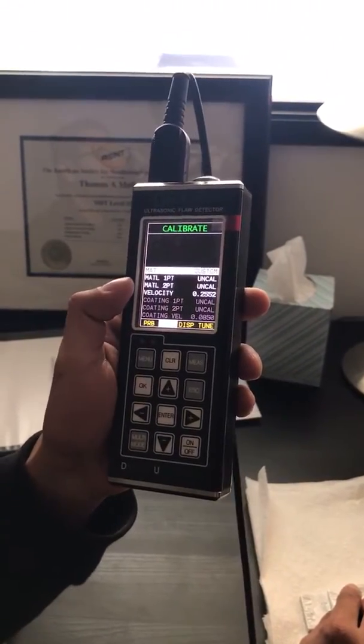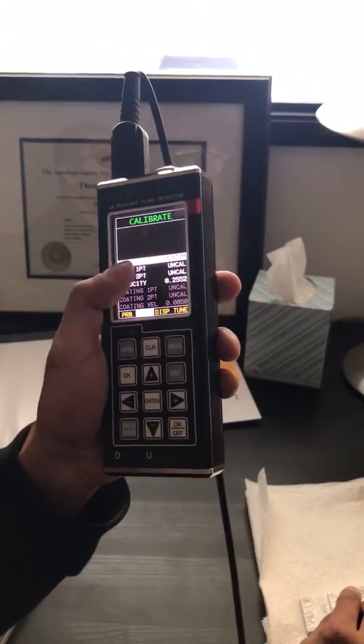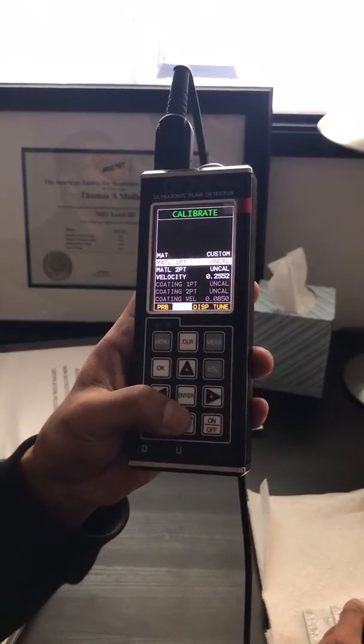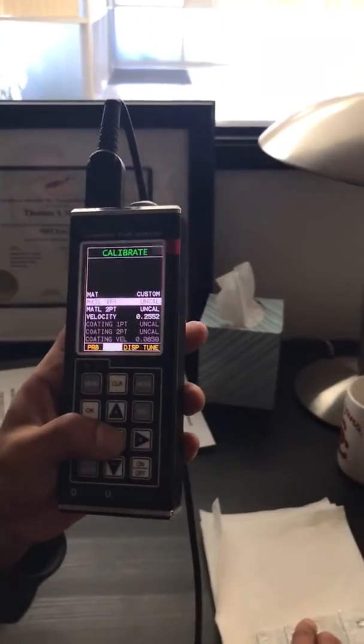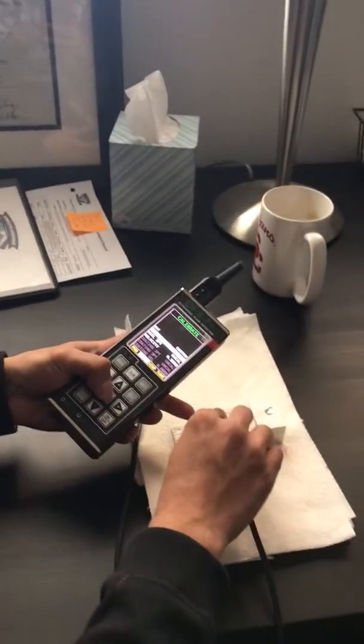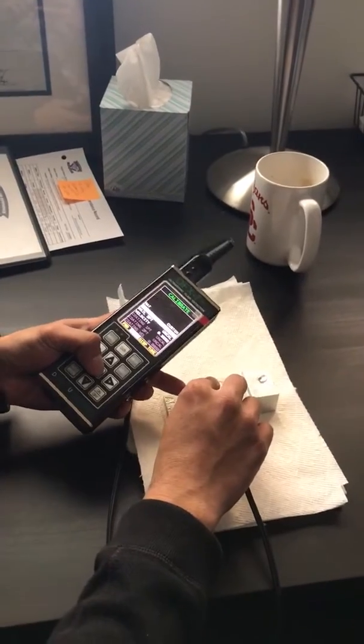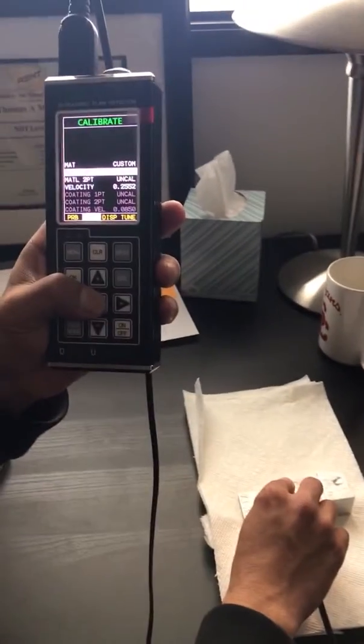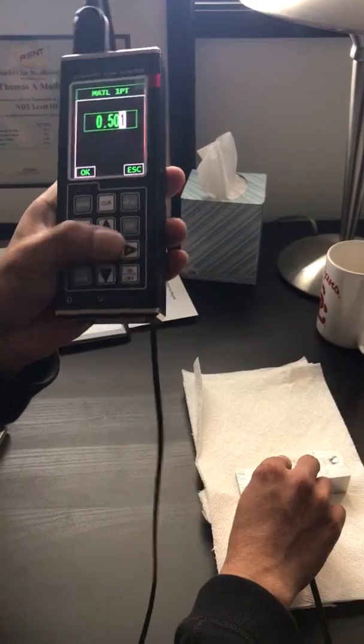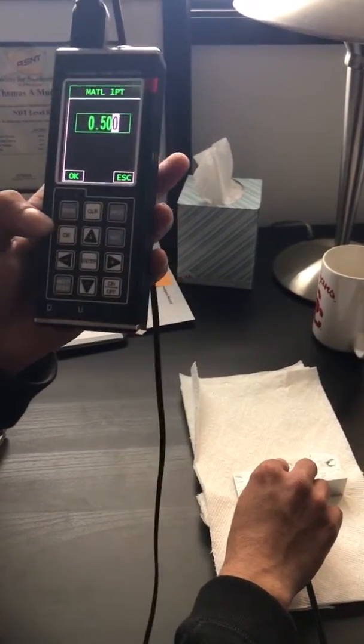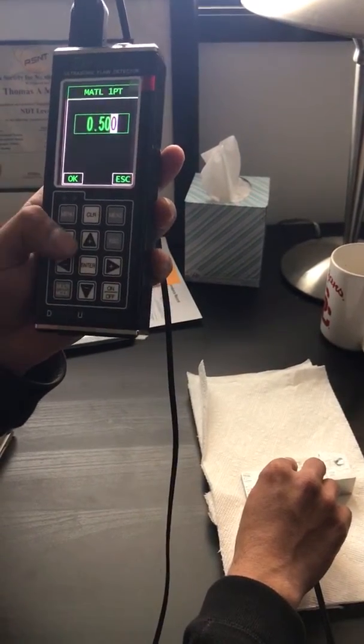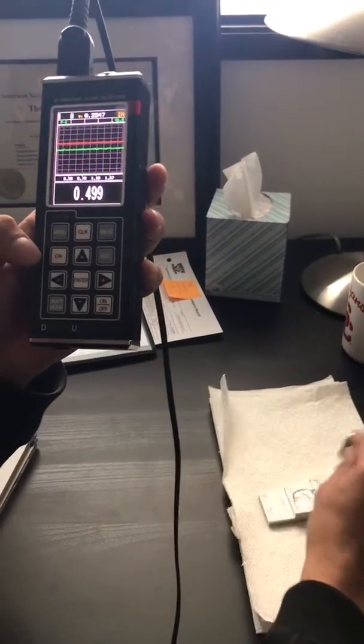It's a two-point calibration, right? So point one, I have to move on point one and hit enter. But make sure that the probe is sitting firmly on your first thickness, which is half inch. So I hit enter, it gives me the option to fine-tune it. Let's make it 500, hit okay.